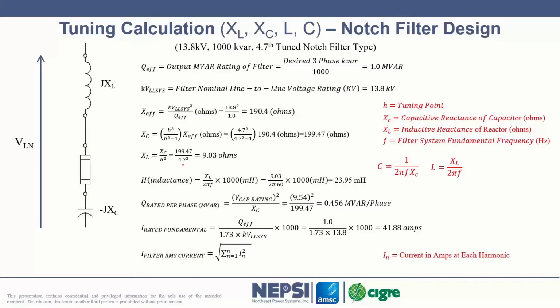This is the tuning point calculation. This is the tuning calculation. This is how we come up with the values of XL, XC, values of L, and values of C. I won't get into the equations too much, but this is the simplicity of it. The spreadsheet tool we have basically powers these equations. What's key here is that we come up with a value of Q effective. What is the megavar output of the filter? How much reactive power do you want? Remember, that's the first rating for a harmonic filter. And from there, we come up with a value of Q effective. We can come up with a value X effective based upon Q effective. And really that represents the combined impedance of these two at 50 Hertz. And from there, we can then calculate X of C and X of L based upon a tuning point.